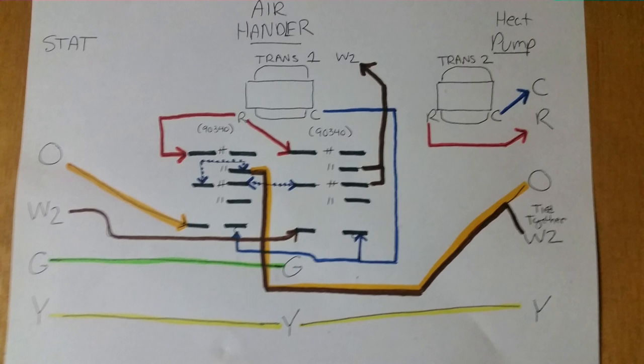But the real thing happens whenever defrost occurs. That's what makes it so difficult to plan out. So we see our O and W2 tied together. So when defrost occurs, W2 and O are both energized. Now the O is energized from the outdoor unit and travels to the reversing valve, which is also in the outdoor unit. So we don't really have to worry about that one.